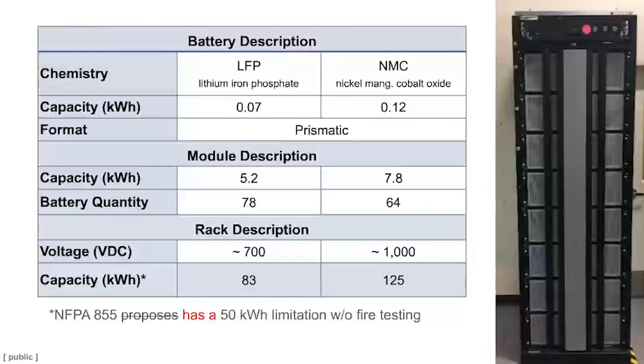And in the world of lithium-ion batteries, energy capacity is fuel. To have a larger energy capacity, you can have more batteries, you're going to have more electrolyte, you're going to start having an increased fuel load. The other thing I want to comment on is that NFPA 855, which is a standard for energy storage systems, now has a 50 kilowatt hour limitation, where if you exceed that limitation, or if you try to, say, reduce the sprinkler protection requirement or the space separation requirements, then you need to run fire tests. And I think a lot of this work supports that statement because, as you'll see, and consider this as you're seeing videos and some data later on, these systems are both larger than 50 kilowatt hours.